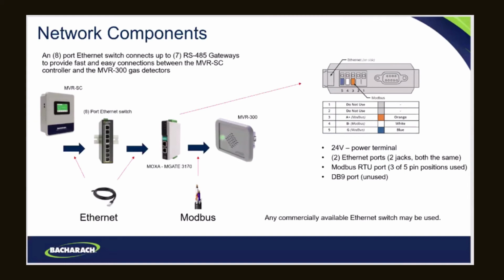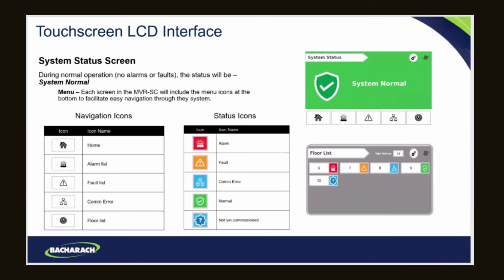I do want to get into the configuration part of it, the Modbus addressing part, because there's a couple different ways you can do that. So I just have a quick comment. There were a couple questions on the consumption first, and I found in the specs that it's 0.44 amps at 24 volt DC. Yeah. Thanks. And for your electrical connection, the blanking plug is a 7/8 diameter hole coming out of the bottom of the SC? That's correct, yes. 7/8. Nice. Thanks, Bob. You're welcome.